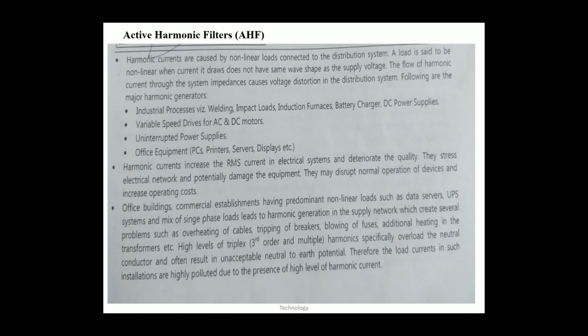The next is active harmonic filters. Harmonic currents are caused by non-linear loads connected to the distribution system. A load is said to be non-linear when the current drawn does not have the same wave shape as the supply voltage. The flow of harmonic current through the system impedances causes voltage distortion in the distribution system. Following are the major harmonic generators.